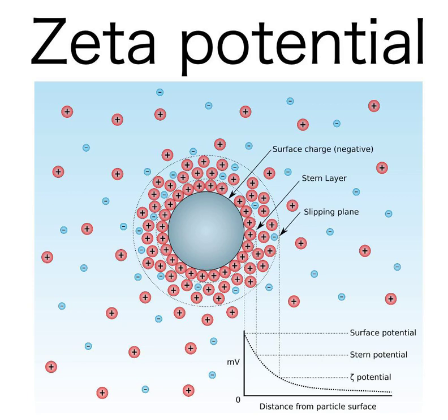Measurement. Some new instrumentation techniques exist that allow zeta potential to be measured. The zeta potential analyzer can measure solid, fibers, or powdered material. The motor found in the instrument creates an oscillating flow of electrolyte solution through the sample. Several sensors in the instrument monitor other factors, so the software attached is able to do calculations to find the zeta potential.